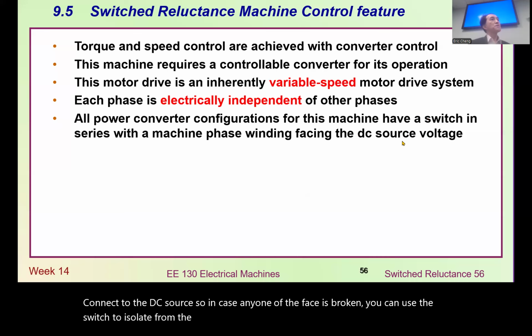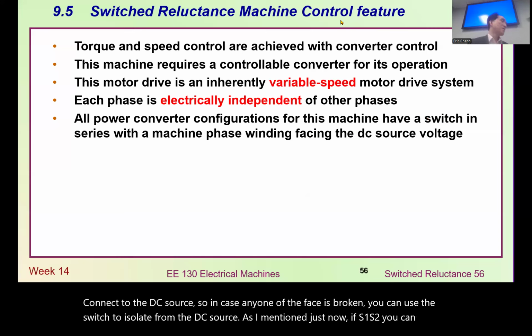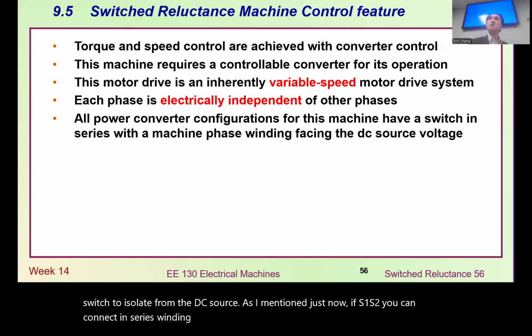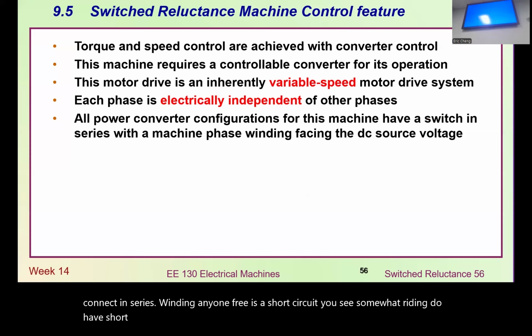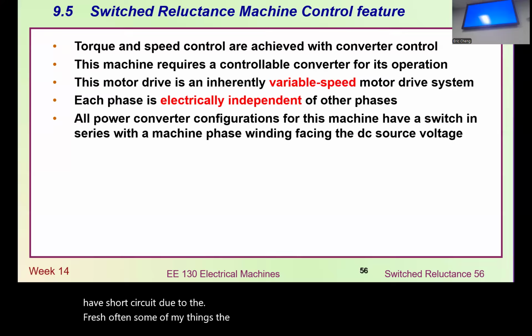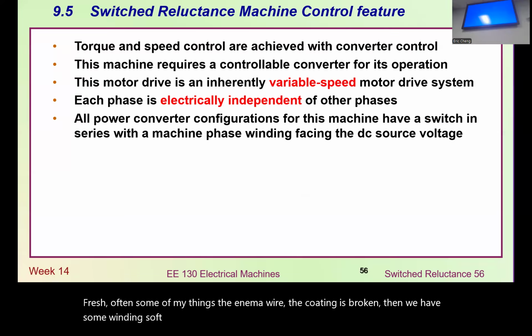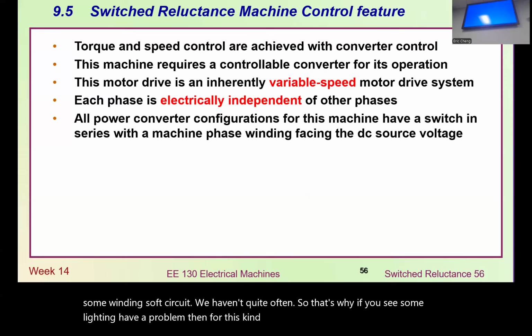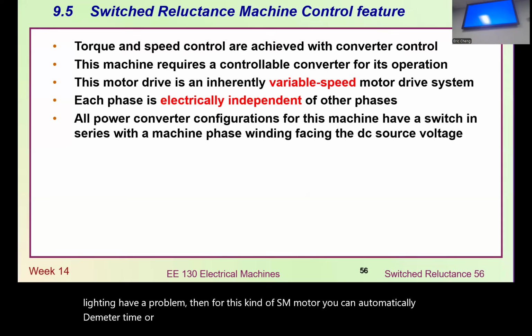As I mentioned, S1 and S2 can connect in series with the winding. If any one phase has a short circuit, some windings do have short circuits due to flashover, where the enamel wire coating is broken, causing a winding short circuit. It happens quite often. So if you see some winding have a problem, for this kind of SR motor, you can automatically demagnetize or disconnect the winding and protect the motor.